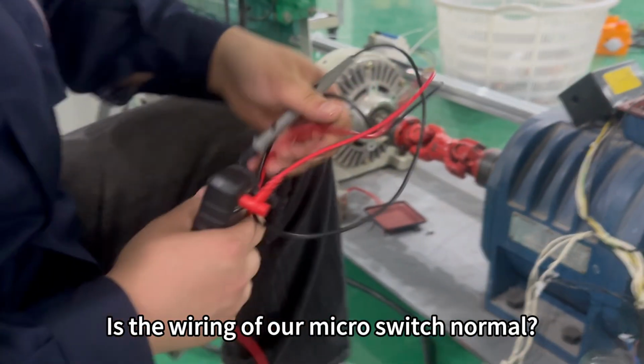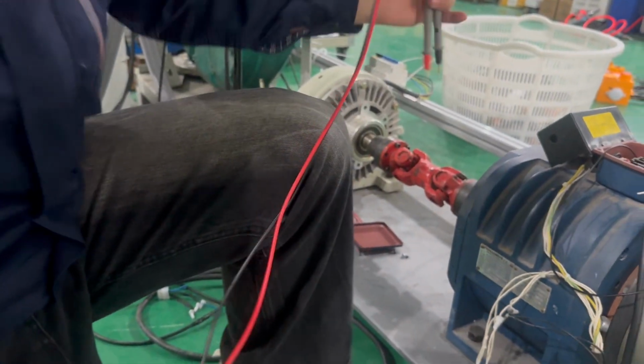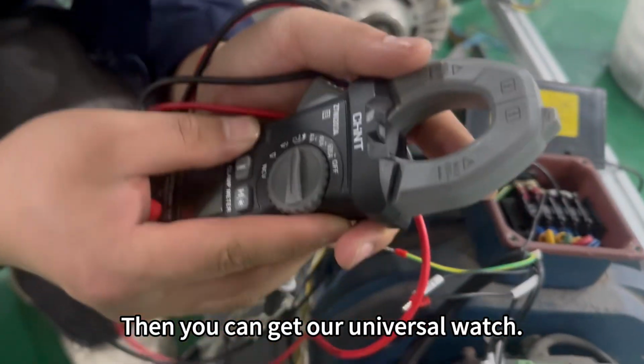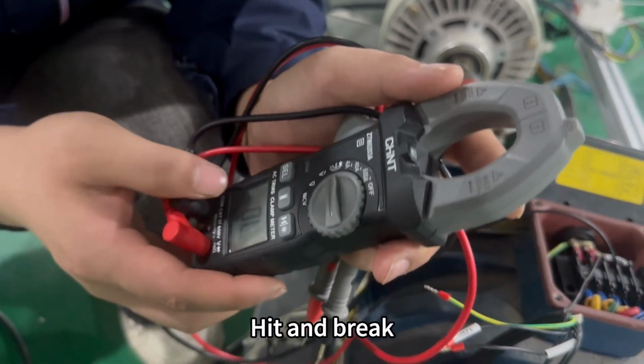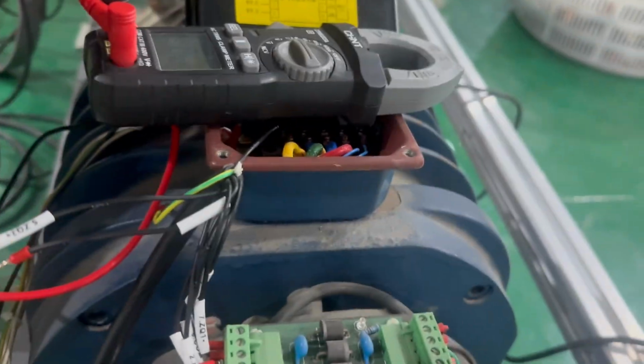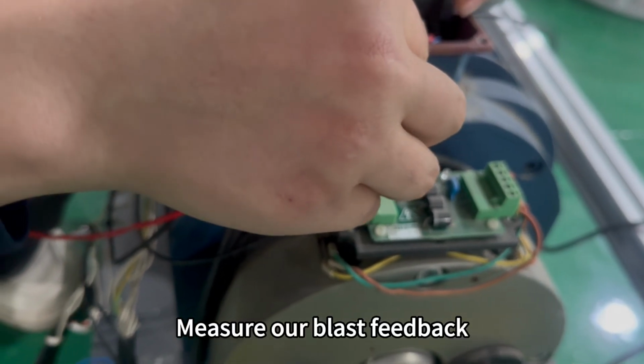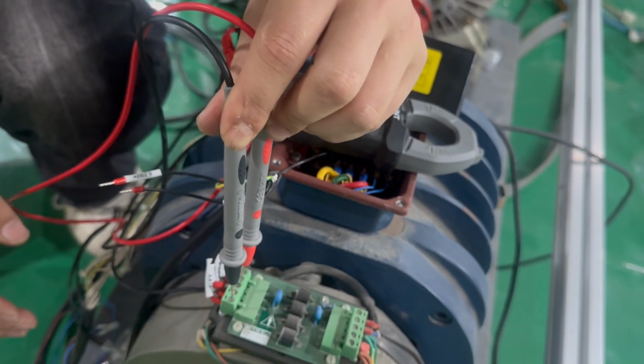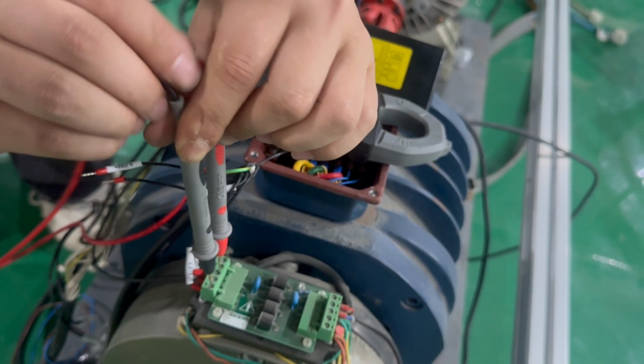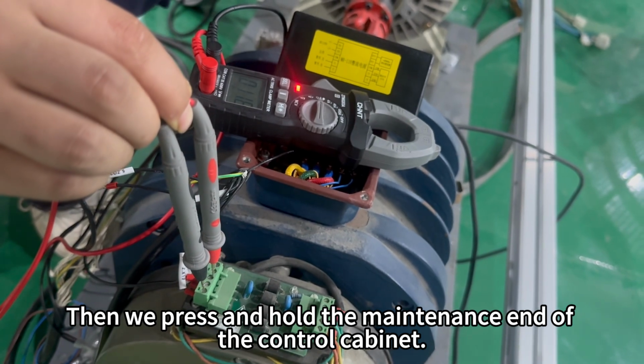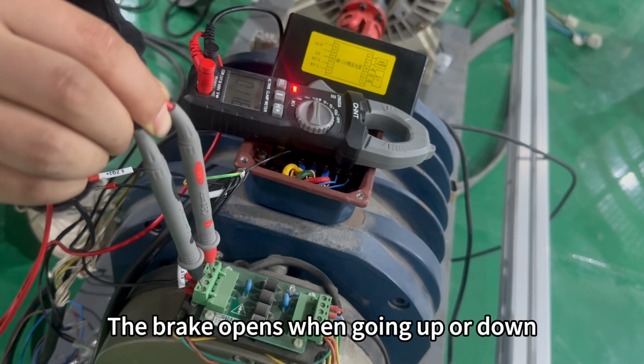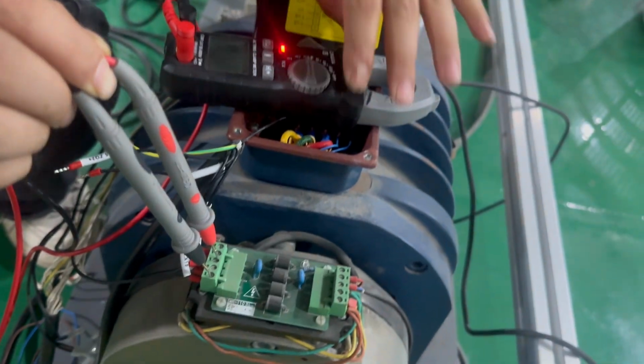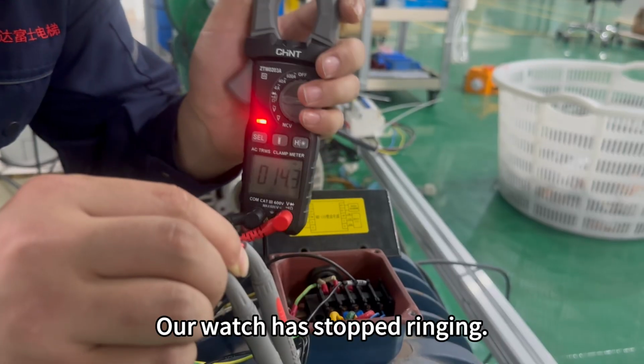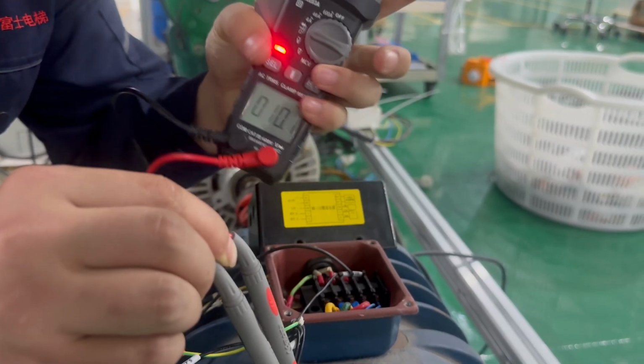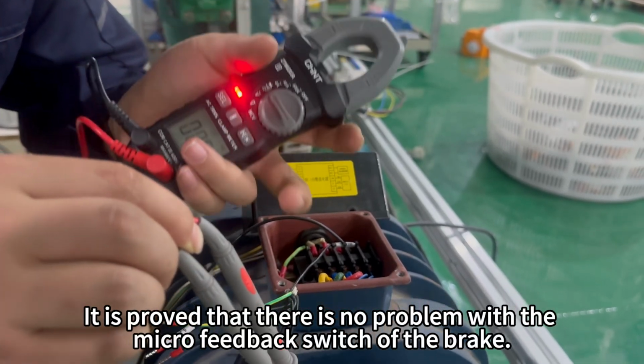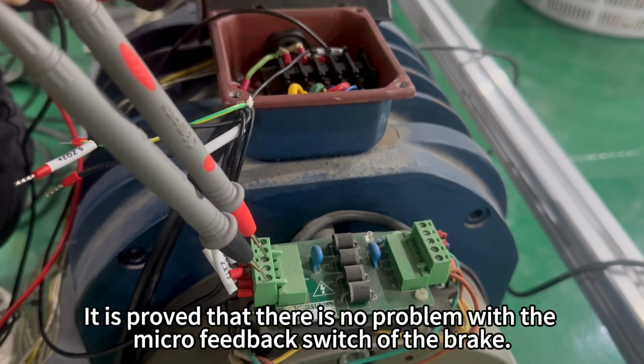Is the wiring of our micro switch normal? Then you can get our universal meter. Hit the brake. Measure our brake feedback. When the brake is not opened, it's normally open. Then we press and hold the maintenance button of the control cabinet. The brake opens when going up or down. If it disconnects, our meter stops ringing. It proves that there is no problem with the micro feedback switch of the brake.